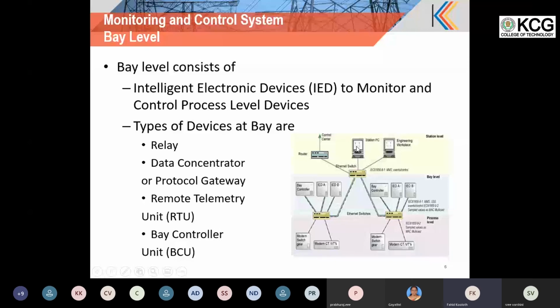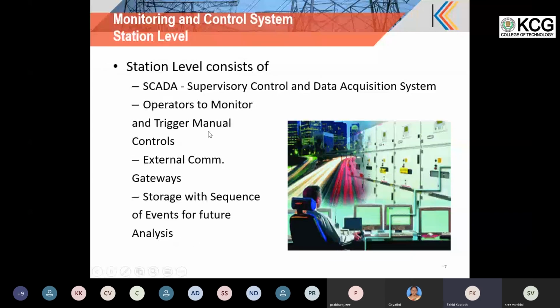So these are multiple equipments that constitute the bay level. Moving on to station level, we will be having SCADA, or what we call a supervisory control and data acquisition system, to monitor and control all the items in process as well as bay level. Then manual triggers and manual commands can be given at the SCADA system. An external communication gateway can be there, from one station to another station or station to control center. Multiple communication scenarios are there. Then storage of events for future analysis, alarms and events can be there at the station.